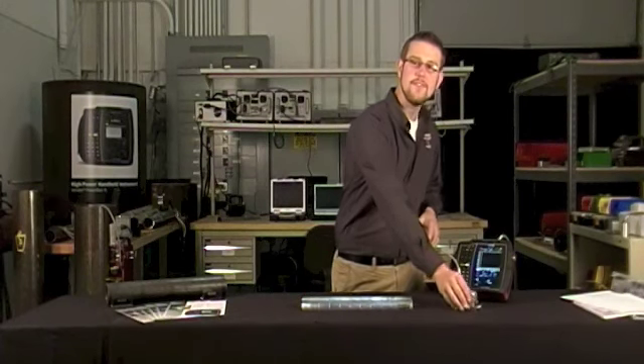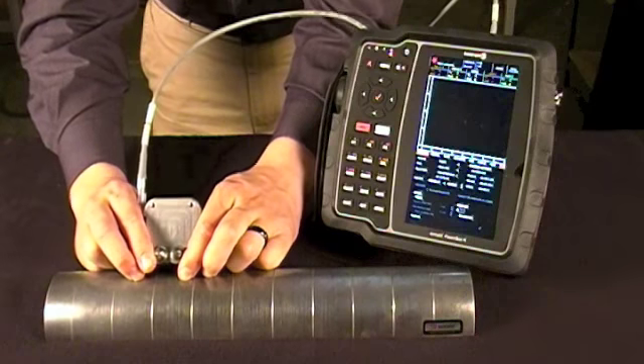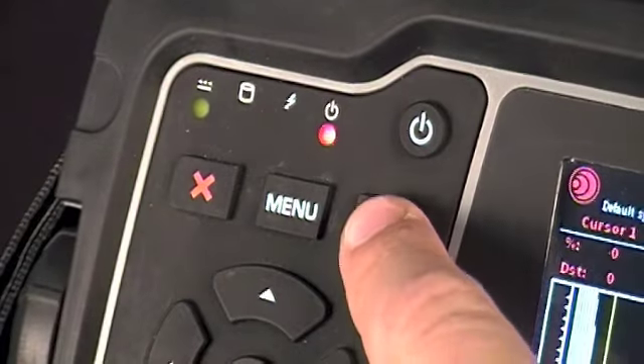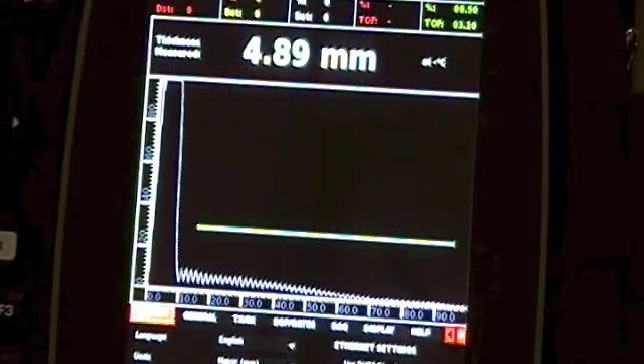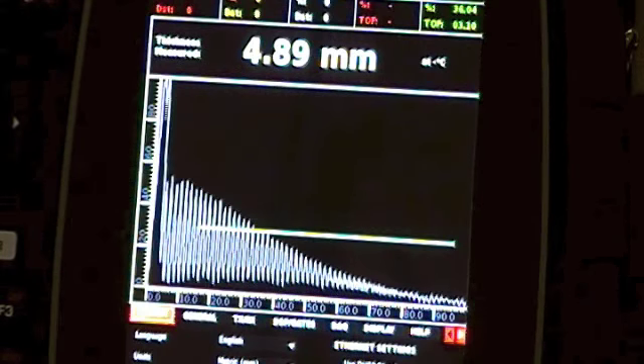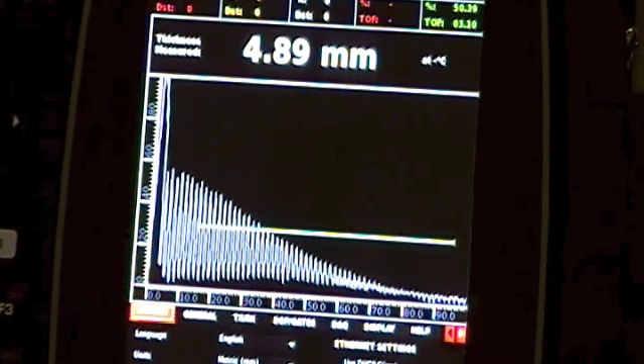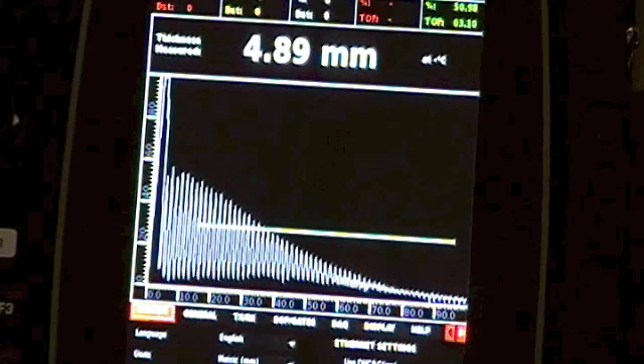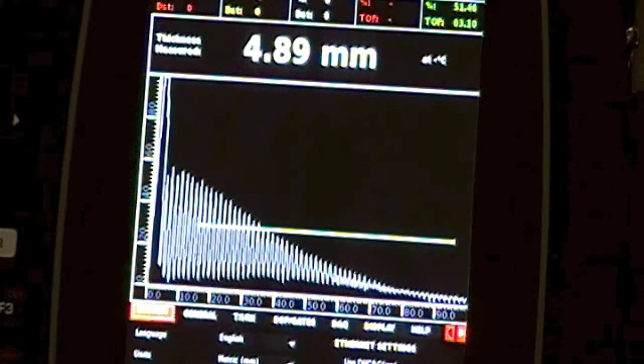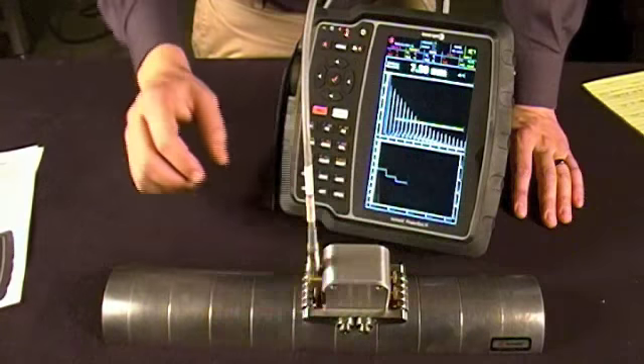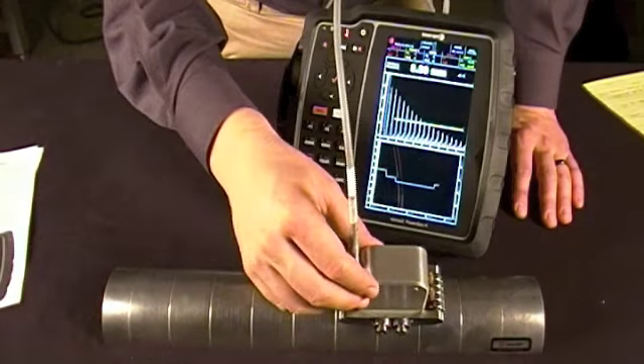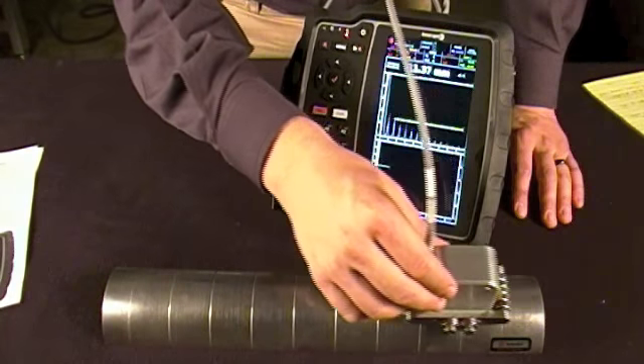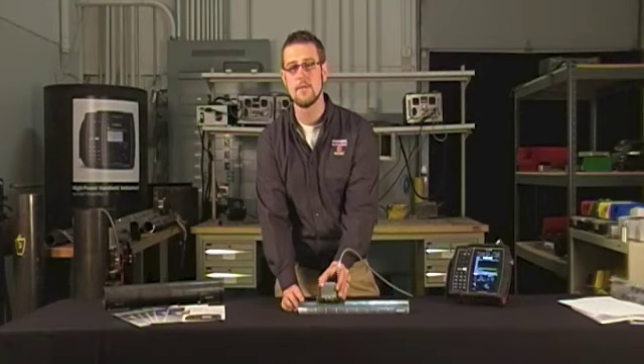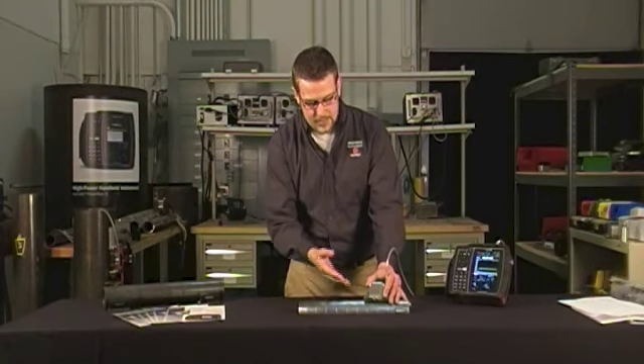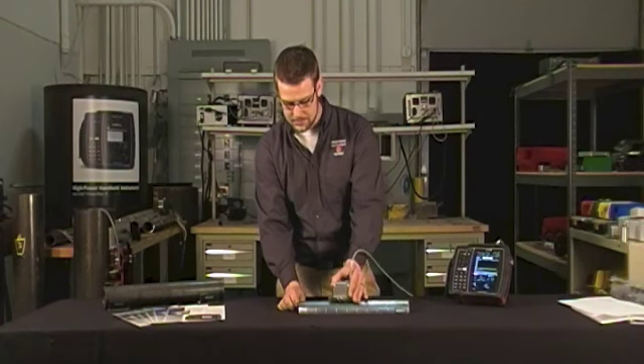To begin, carefully place the sensor on the testing surface and press the play button to begin analysis. You'll quickly see the A-scan displaying one or more back wall signals, and it will provide you with a default metric reading of the thickness. As I move the sensor freely along the sample, the thickness reading is continually displayed, and a strip chart can be activated to display the thickness trend. Another great benefit of thickness measurement with EMAT is that the measurement is conducted completely free from the use of couplant.